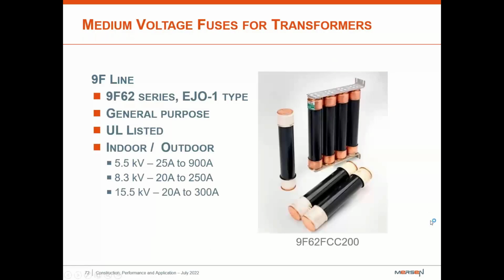It's also known as the EJO-1 type. This is going to be for general purpose. They are going to be UL listed. Indoor, outdoor use, 5.5 kV, 25 amps up to 900, 8.3 kV for 20 amps up to 250, and for 15.5 kV, we're going to have 20 amps up to 300 amps.